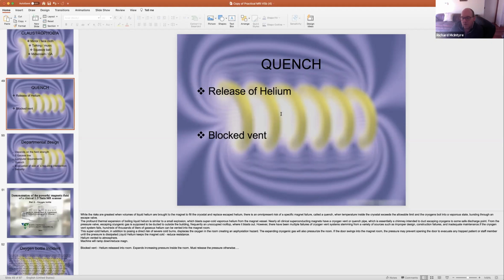So we know that if we didn't use liquid helium, we energize these coils, and the energy goes around in a circle. Eventually it's going to heat up and get resistance and that energy is going to stop. Start it again, next energy comes in, goes around, heats up, resistance and stops. So what we want to do is bathe these coils in liquid helium. What's going to happen then is that energy is going to keep going round and round and round. The current's not going to heat up and it's not going to stop.